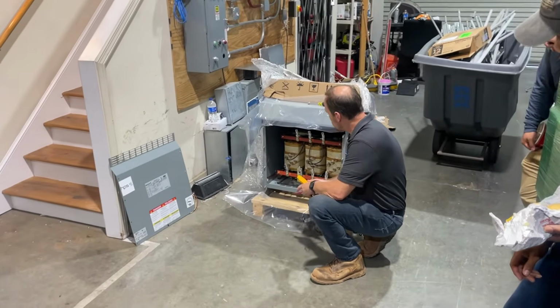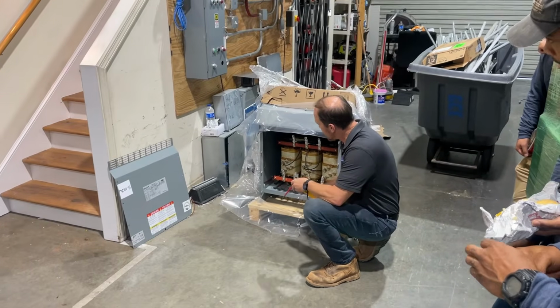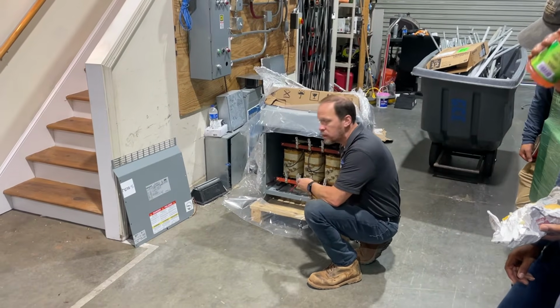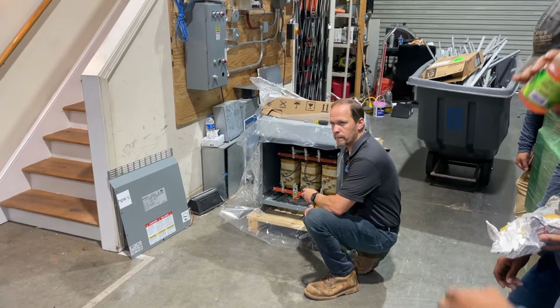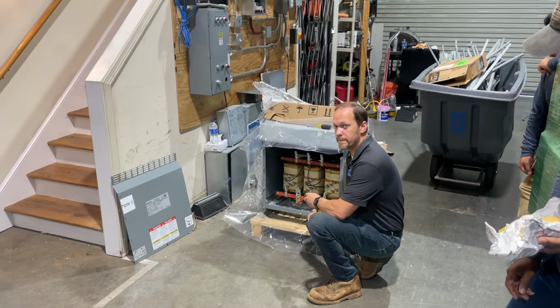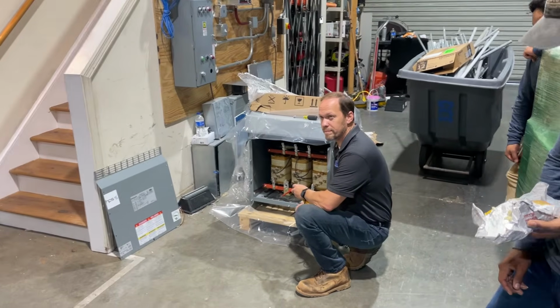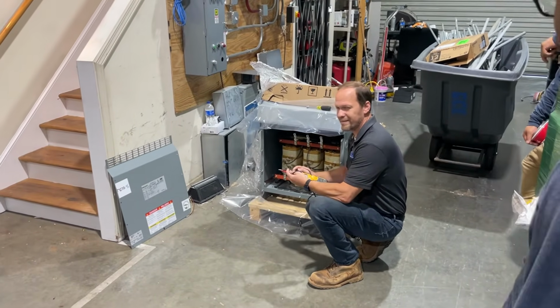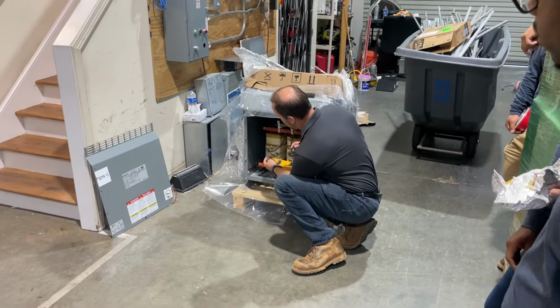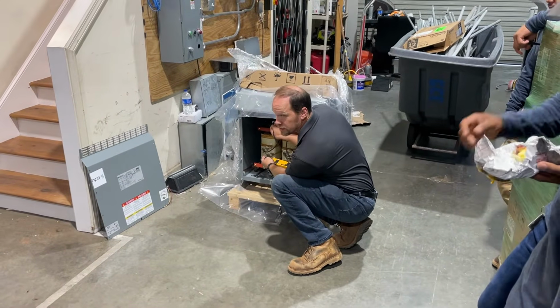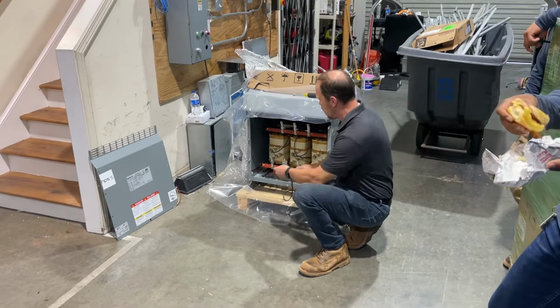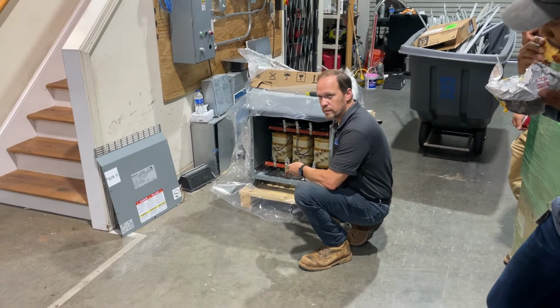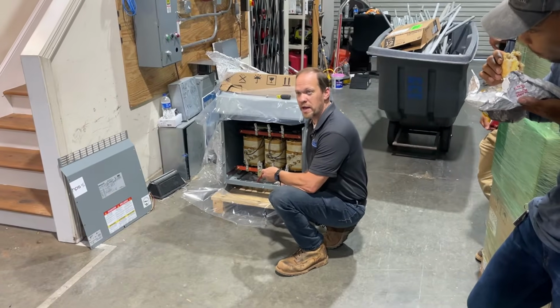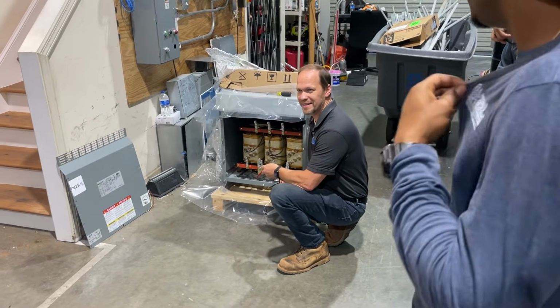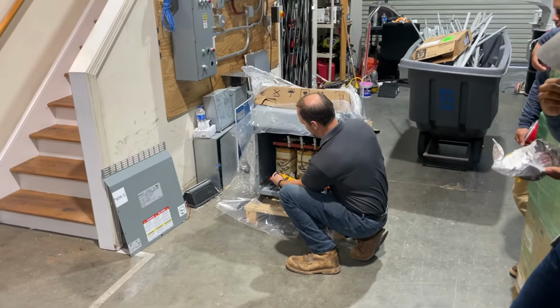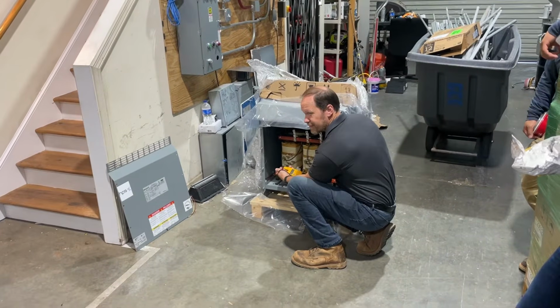Now, on a three-phase transformer, what is your expectation if I put my continuity test between H1 and X1? Is it going to ring? No. No connection. Only one connecting is the auto transformer. H1 to H2, yes or no? Come on, be bold here. I say yeah. It's going to be connection. It's on the same side.